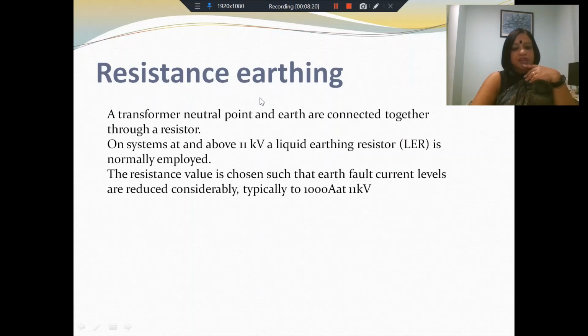Impedance earthing, the first kind of impedance earthing is the resistance earthing. So when you connect the transformer neutral point to the earth, you include a resistor between them. So the transformer neutral point and earth are connected through a resistor. This resistor is often a liquid earthing resistor, especially if you're dealing with systems above 11 kV. The liquid earthing resistor is also called an LER. The resistance value is chosen depending upon the kind of fault levels you expect. And your objective is to reduce the fault current as far as possible. So typically, you may be able to conduct 1000 amperes at 11 kV through the resistance from neutral to ground. So that is the kind of capability that a resistance earthing might have.